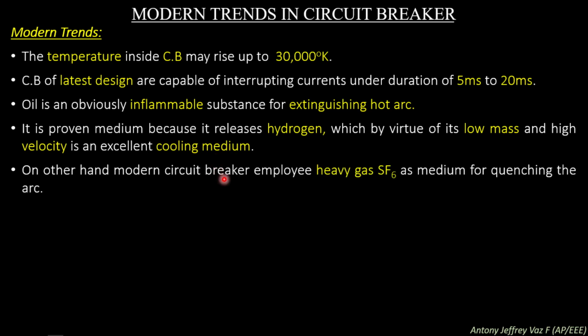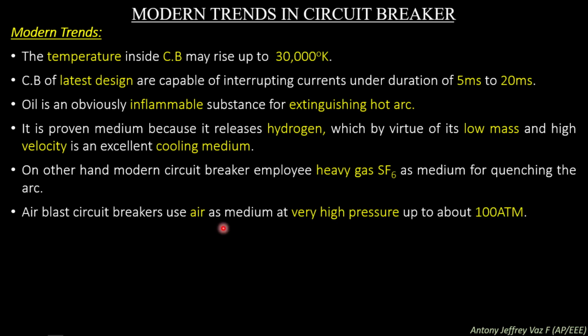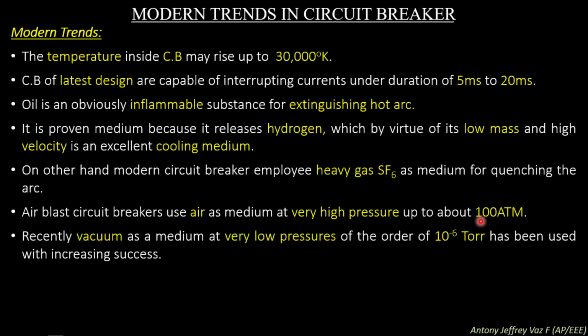On the other hand, modern circuit breakers employ heavy SF6 gas as a medium for quenching the arc. So in circuit breakers we can use SF6 gas as a medium to quench the arc. Air blast circuit breakers use air as the medium at very high pressure, up to 100 atmospheres. So when air is used in circuit breakers as a medium, the pressure should be increased to a maximum value of 100 atmospheres.